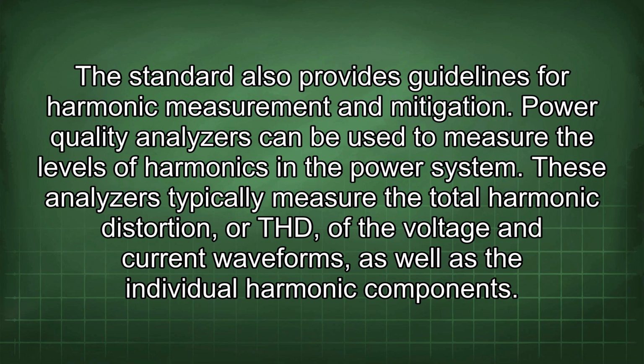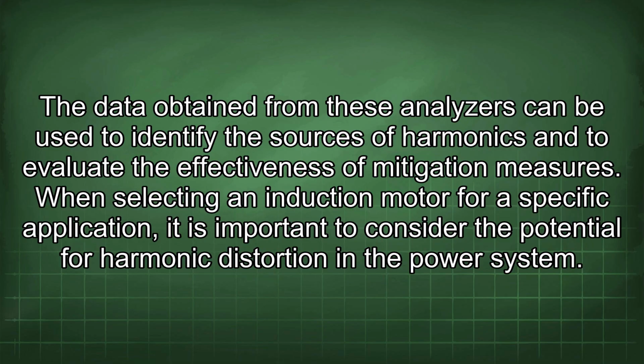Power quality analyzers can be used to measure the levels of harmonics in the power system. These analyzers typically measure the total harmonic distortion, or THD, of the voltage and current waveforms, as well as the individual harmonic components. The data obtained from these analyzers can be used to identify the sources of harmonics and to evaluate the effectiveness of mitigation measures.